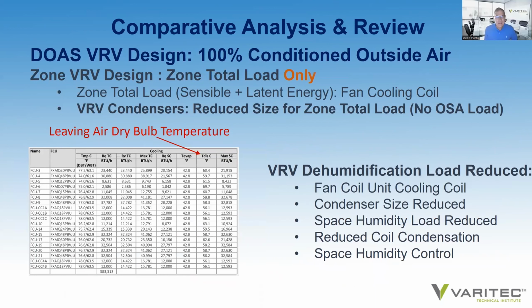If we look at decoupling the outside air, the VRV system sees only the zone total load. Consequently, the dehumidification load at the fan coil units is reduced, the condenser sizes are reduced, and the space humidity load seen at the indoor air handler is reduced. You have reduced coil condensation and deeper space humidity control.